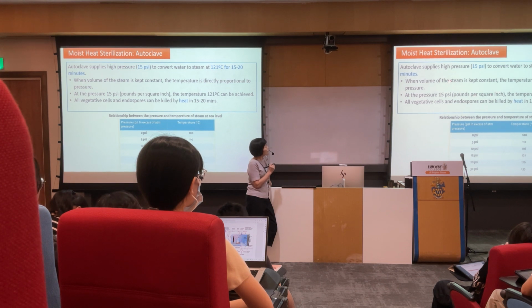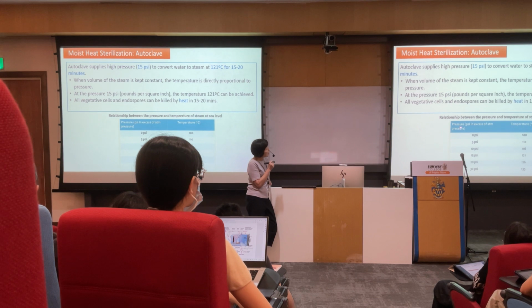So when you keep the volume of steam constant, if of course inside the chamber of the machine the volume of steam is constant, then the temperature will be proportional to the pressure. So that is a table indicating that when you increase the pressure, you actually increase the temperature in proportion. Alright?